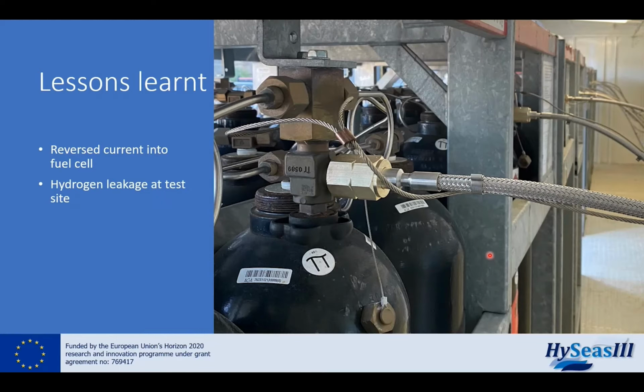During the integration testing, we got a gas detection alarm from the hydrogen storage container. The ESD shut down the whole system, but the leakage continued. The test team then notified the fire department and the management at the test site and at KM. The fire department again notified the police and the ambulance as a part of their procedures. The next couple of hours was kind of hectic.